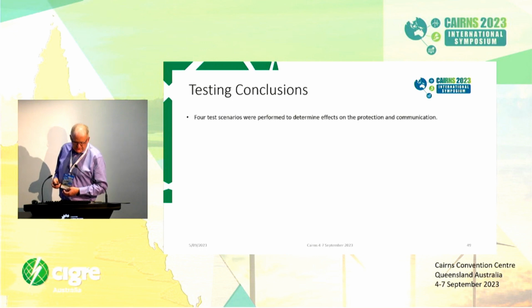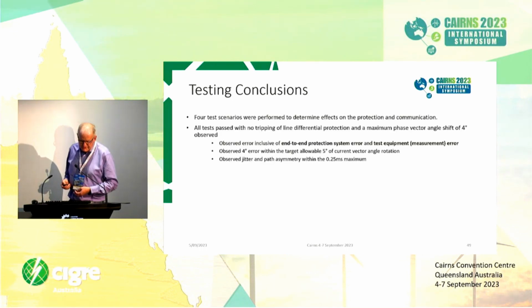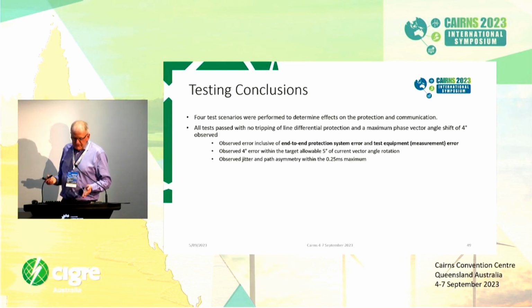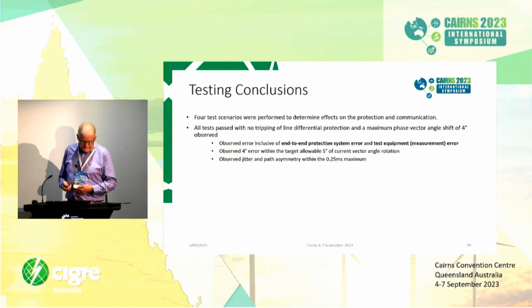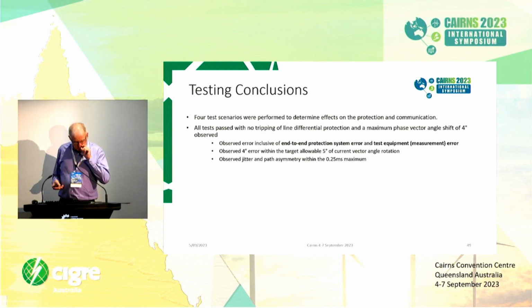So testing conclusions, we ran 4 test scenarios to determine the effects or the failure modes and effects for both protection system and communication system failures. All the results, by the way, are inclusive of the actual system errors, but also the test equipment measurement errors. All the test equipment was synchronised from GPS, so we'd expect that to be very minimal, but it still has to be noted that it does include your testing errors as well. It's not just the actual system.